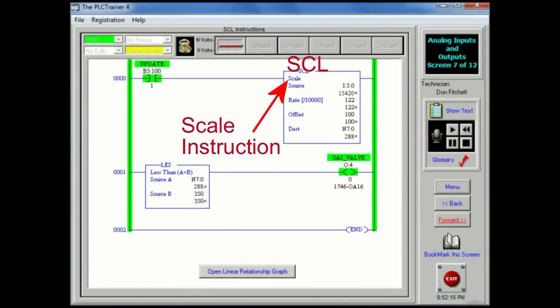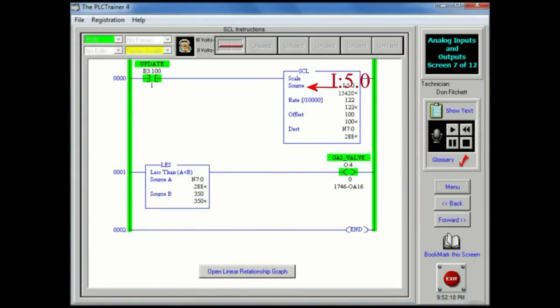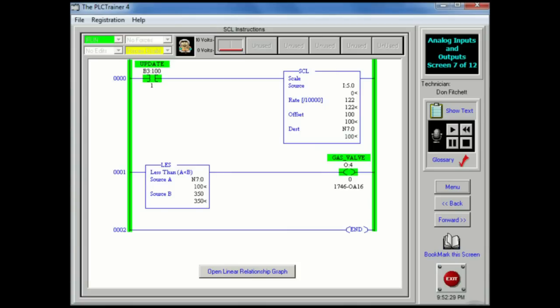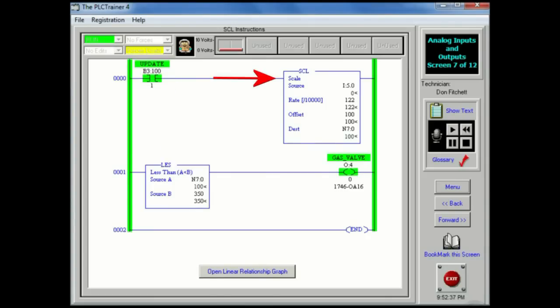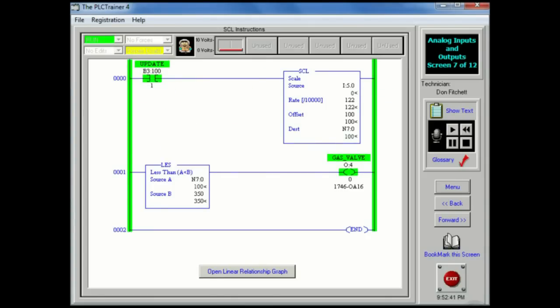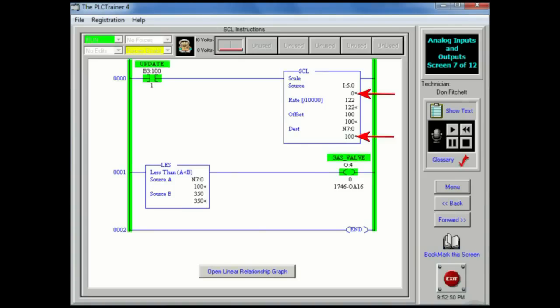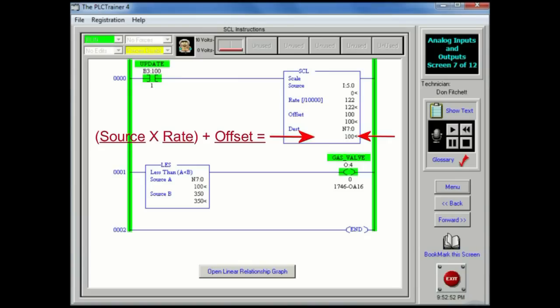The SCL or scale instruction is used to scale data from an analog module and bring it into the limits prescribed by the process variable. This process variable may be either an arbitrary number or engineering units, such as pounds per square inch, degrees Celsius, ounces, etc. When rung conditions are true, this instruction multiplies the source by a specified rate. The rounded result is added to an offset value and placed in the destination. The equations used in calculating the linear relationship between the input and the scaled output are: Scaled value equals input value times rate plus offset.